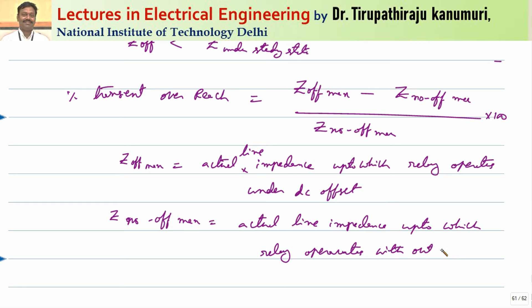The first one is Z offset, the maximum value. Z offset maximum value will be the actual line impedance up to which the relay operates under DC offset. And the second one is Z no offset maximum, so the actual line impedance up to which the relay operates without DC offset.